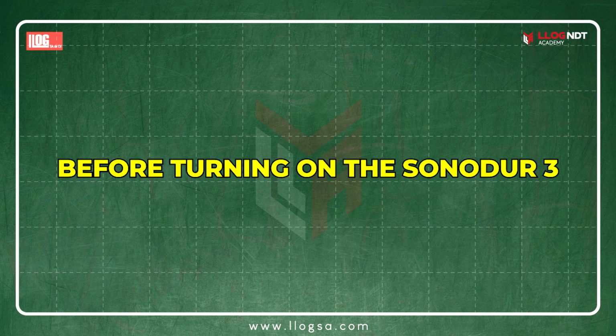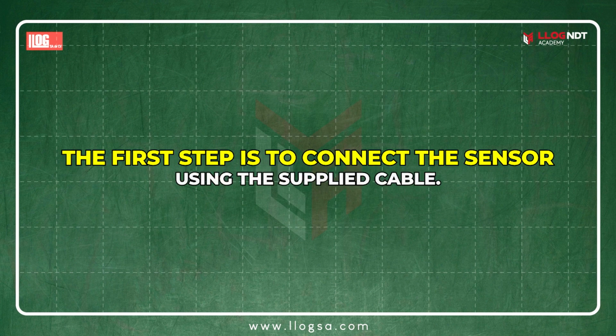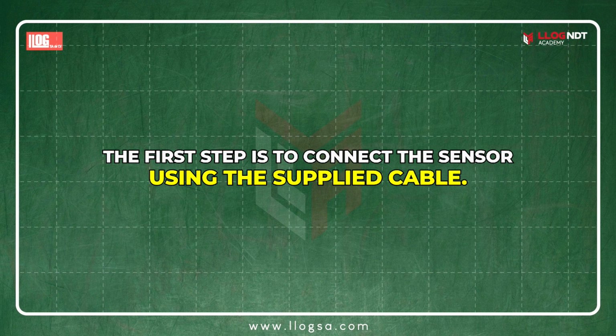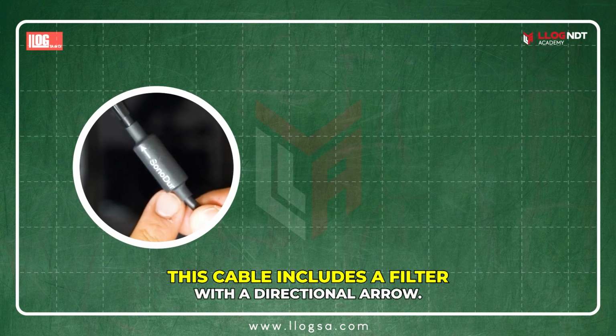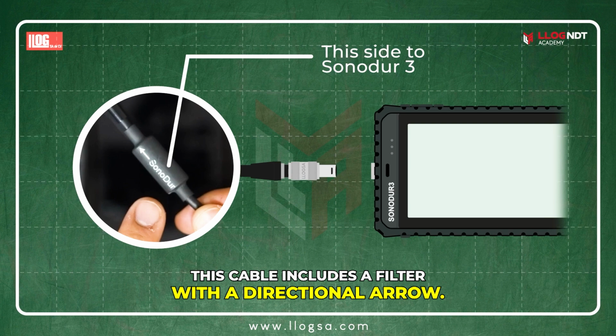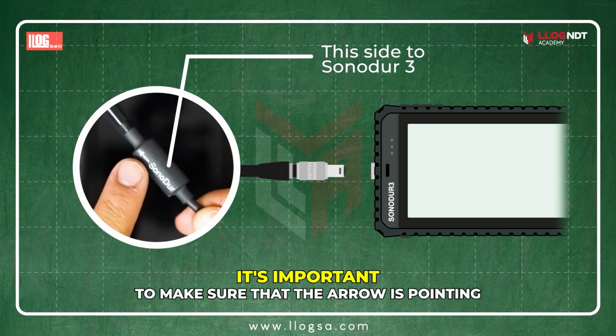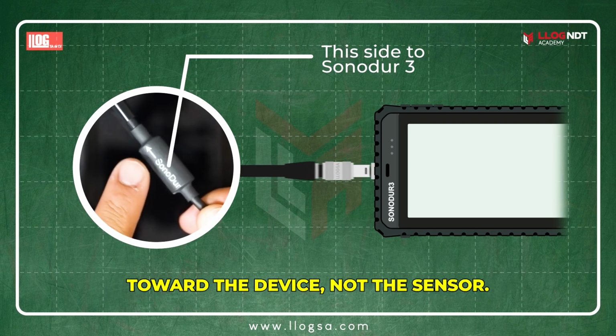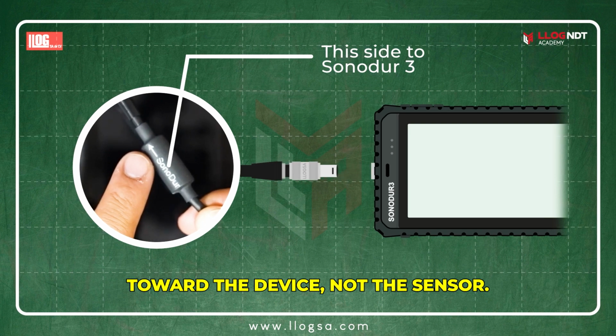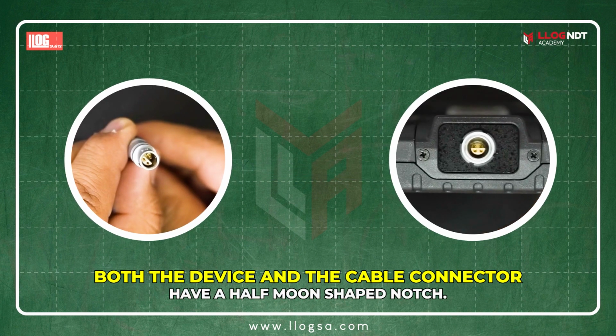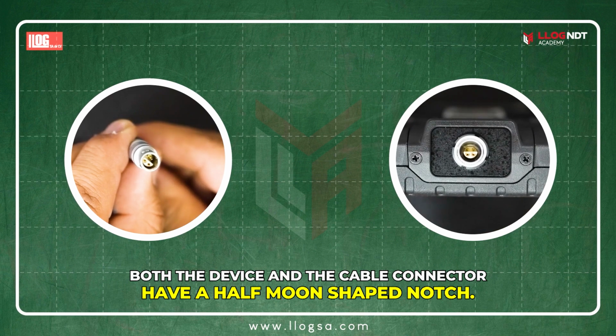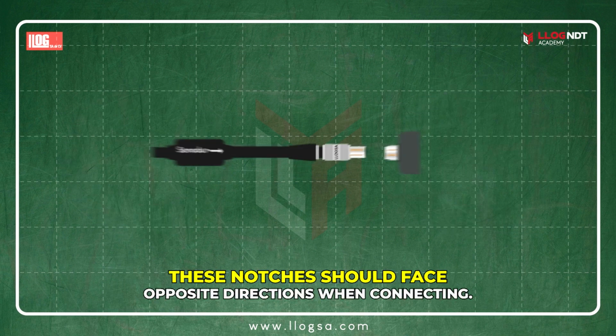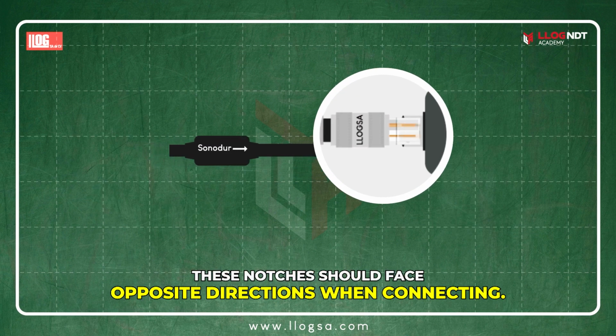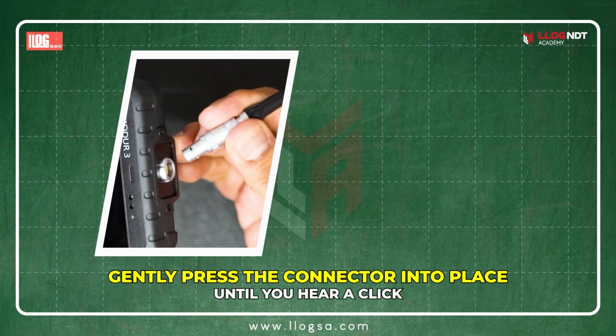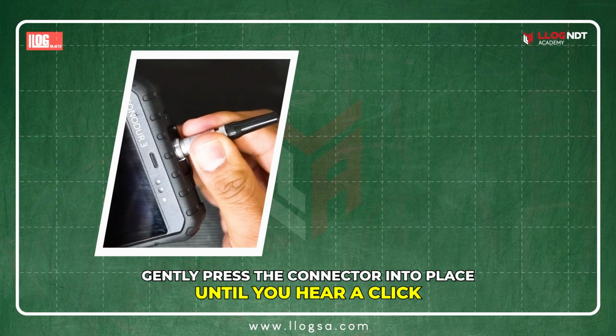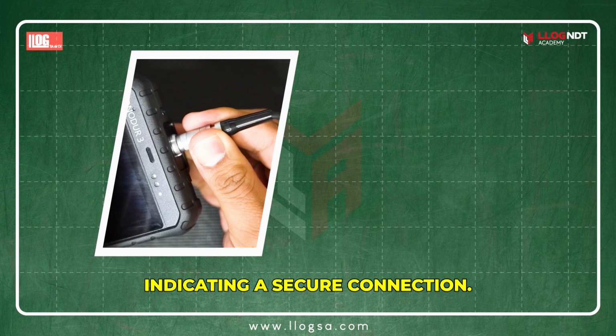Before turning on the Sonodur 3, the first step is to connect the sensor using the supplied cable. This cable includes a filter with a directional arrow. It's important to make sure that the arrow is pointing toward the device, not the sensor. Both the device and the cable connector have a half-moon shaped notch. These notches should face opposite directions when connecting. Gently press the connector into place until you hear a click, indicating a secure connection.